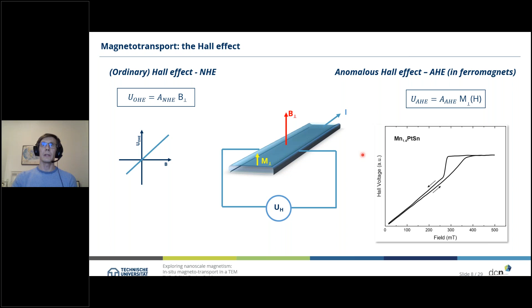First of all, we want to know how large the magnetic field is which we generate at the area of our sample. That is measured here using a standard commercially available Hall sensor, shown here in the image in the inset on the top. We calibrated that Hall sensor in a cryostat. These Hall sensors are linear in response to the applied magnetic field, which is quite nice, but you still need to know the calibration, of course.